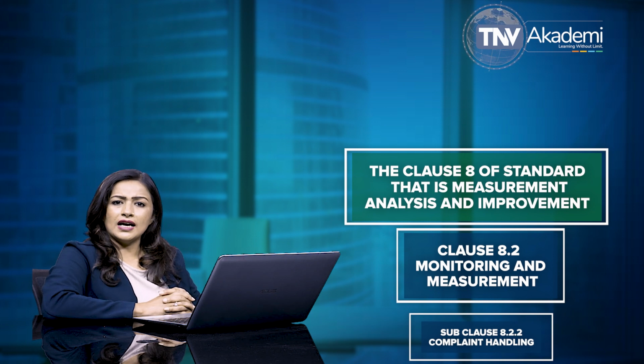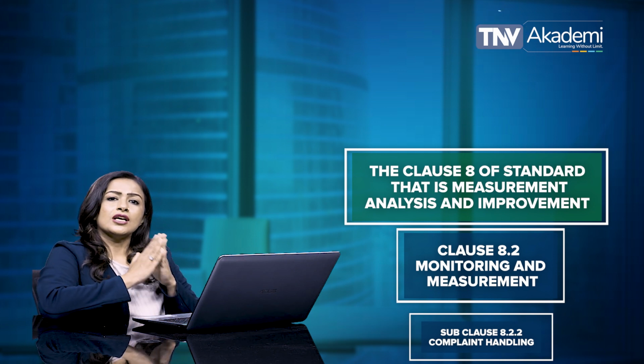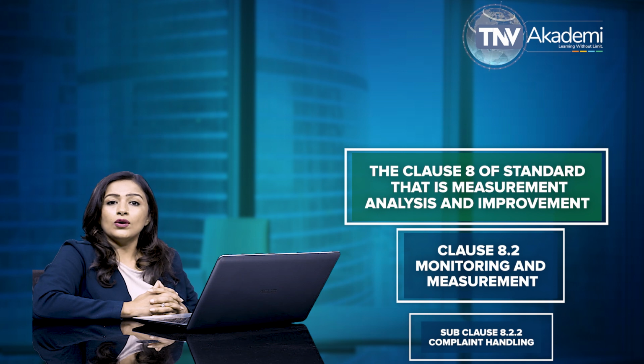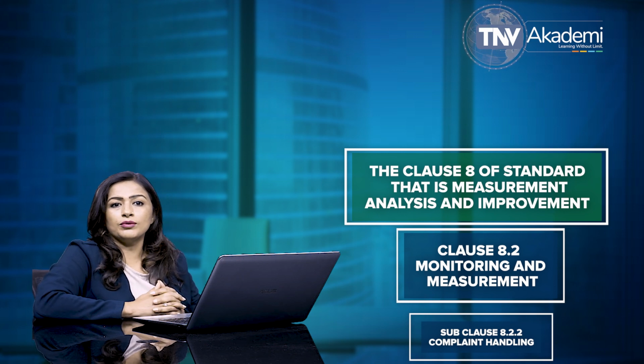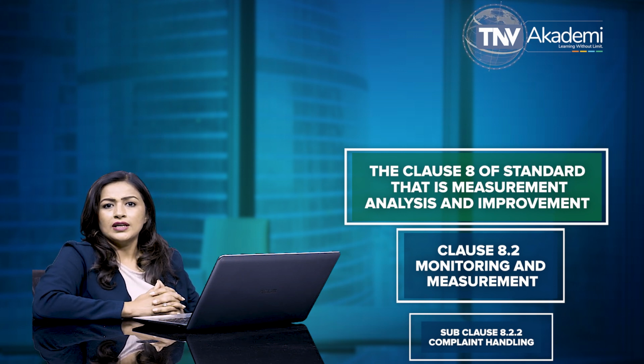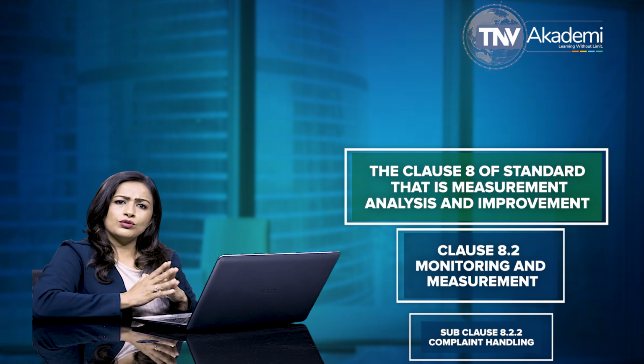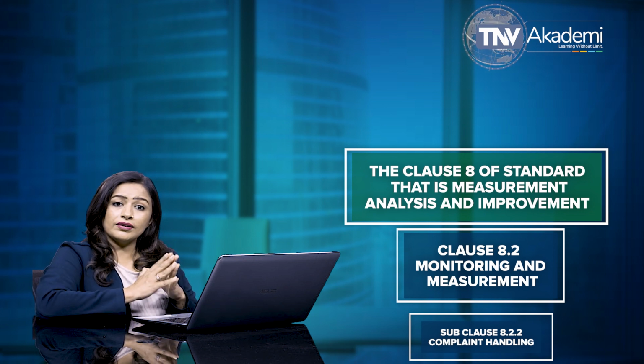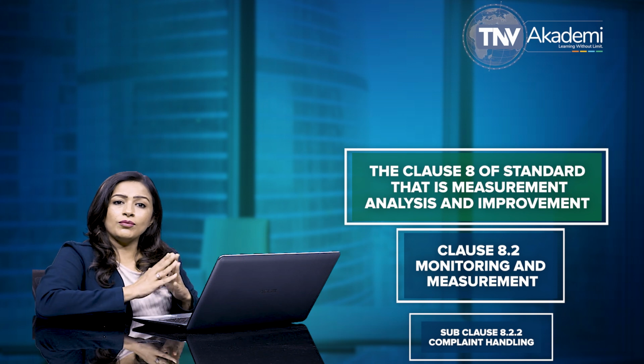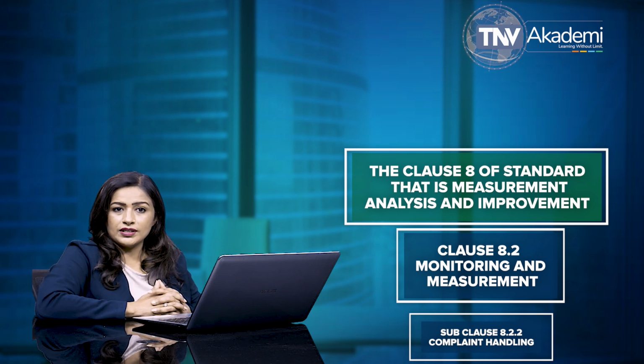This clause says that if any complaint is not investigated, the organization is required to document the justification. An organization is also required to document any correction or corrective action resulting from the complaint handling process.